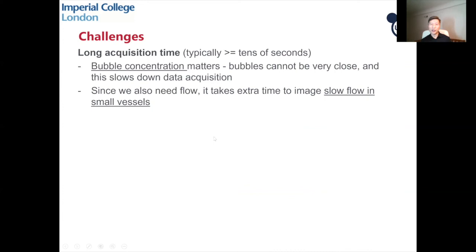It looks wonderful, but there are lots of challenges that still exist. One key challenge is acquisition time — currently it is quite long, typically tens of seconds, some even more for 3D scanning. Bubble concentration matters: we want to localize individual bubbles so they can't be very close. Using lower concentration slows you down because you need to accumulate a sufficient number of bubble signals.